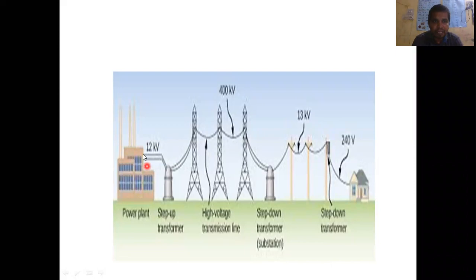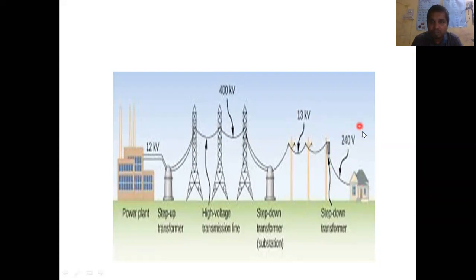A typical system will have power generation, step-up transformer, power transmission, step-down transformer, and power distribution. A typical representation of the power system: a power plant — anything, like a photovoltaic cell. You can see a solar power plant where 12 kV is generated, then a step-up transformer steps it up to 400 kV. Through the transmission line, it is stepped down further in the substation to 13 kV, then stepped down further for the distribution level to 240 volts.